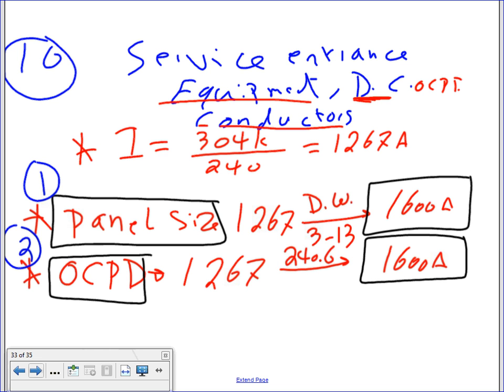You buy a 1600 amp circuit breaker and dial it down to just above this one. I have 1267, which is close to 1300, right? You dial the 1600 down to 1300 and size your feeders based on that. But we're assuming these are fixed, non-adjustable circuit breakers, highly unlikely though. So that's the size of the panel.